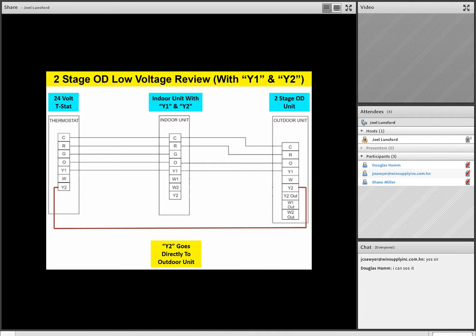In addition, our Y2 from the thermostat goes straight outside, because on our two-stage outdoor unit, again, we're going to have a Y2 output from the outdoor unit to bring on second stage. And again, this could be the result of outdoor temperature.